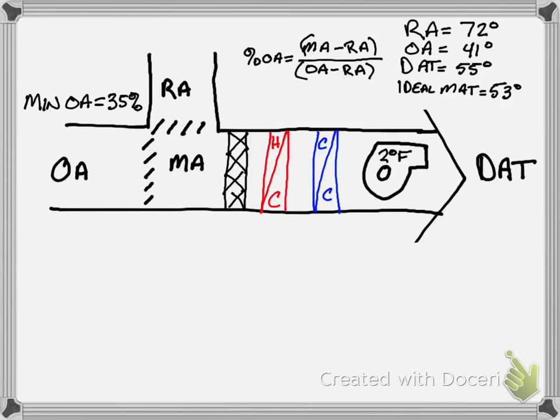So what we do is we take the values that we know and we test our hypothesis to see if we can meet our heating and cooling load with economizer control only. We're going to plug this into the equation here. Percentage of OA equals 53, our ideal mixed air temperature, minus 72 over 41 minus 72.